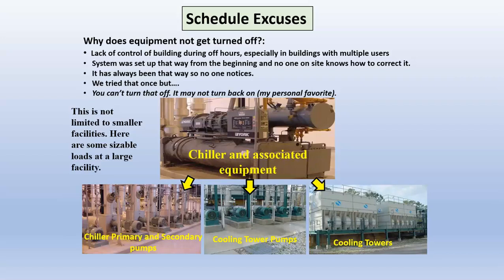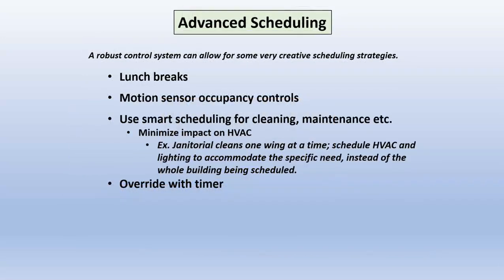This is not limited to smaller facilities. These pictures are actual loads that ran all the time that didn't need to. Those secondary pumps are about 30 horse each, but those cooling tower pumps are 100 horsepower each. You're talking a lot of money. So, advanced scheduling. We talked about lunch breaks a little bit. You can also integrate motion sensor occupancy controls into your lighting and your HVAC system. One case where this saved money was in schools. They have a pretty hard schedule. Well, you get a snow day. No one comes in. Big blizzard. Well, the motion sensors, the units would start up as they're supposed to, but then they would detect, hey, no one's in these classrooms, and then they'd shut down and save that day's worth of money.